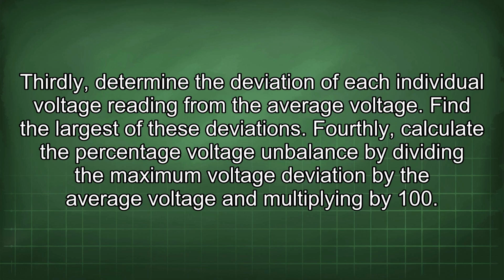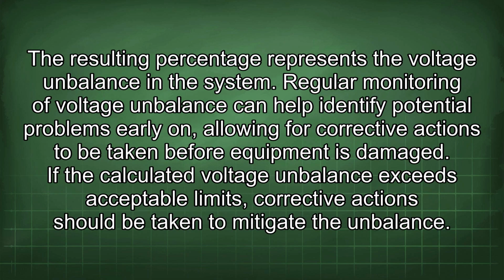Thirdly, determine the deviation of each individual voltage reading from the average voltage. Find the largest of these deviations. Fourthly, calculate the percentage voltage imbalance by dividing the maximum voltage deviation by the average voltage and multiplying by 100. The resulting percentage represents the voltage imbalance in the system.